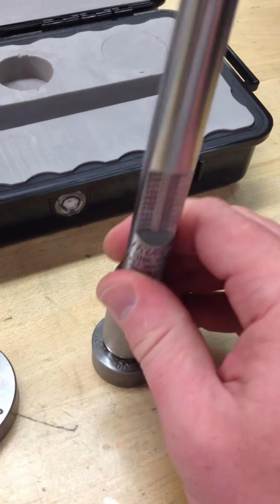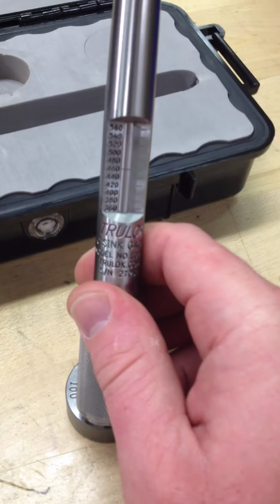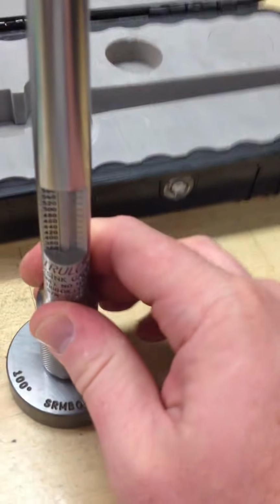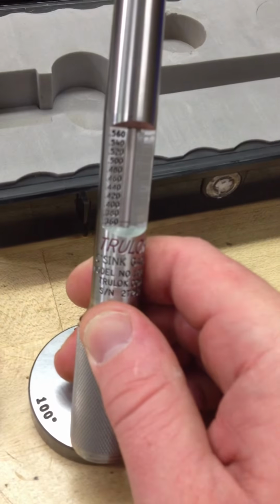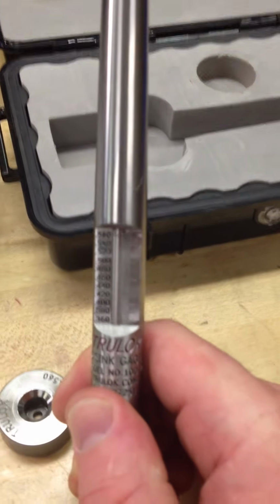I'm going to calibrate it to the 460 block. Take a look at it. It's right at 460. I'm going to pull the pin, and I'm going to go to the bottom side, the 360 block. I'm going to check it. It's right at 360. I'm going to pull the pin again, and I'm going to check it to the top side of the range, which is the 560. And it's right at 560.